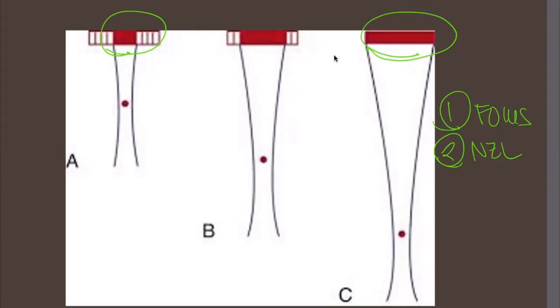So right now I'm using all of my PZTs, which is the same as having a large aperture because my focus is at the bottom of the screen, which means I have a long near zone length. When you move your focus up, it's not like you opened your transducer up and removed some of the PZTs, right? No, the PZTs are still there. You're just not using them. So it's kind of like they're being blocked out for a minute. They're there, they're just not given any electricity, which means they're not ringing, they're not vibrating, they're not oscillating, they're not deforming, they're not sending out a pulse.